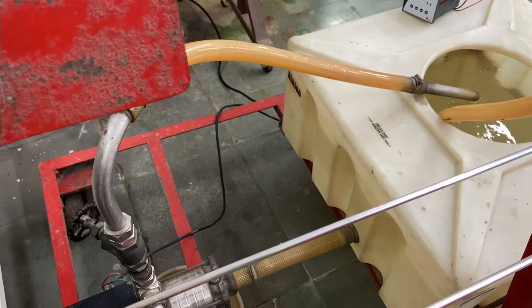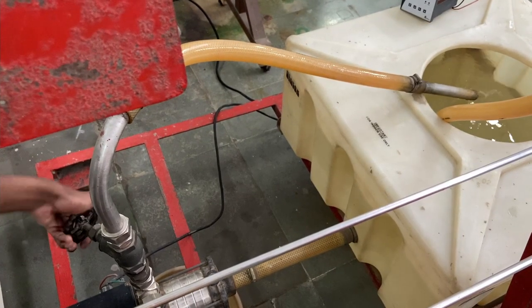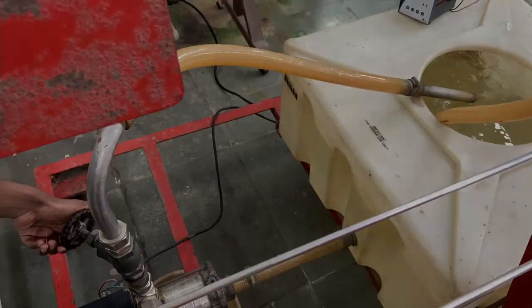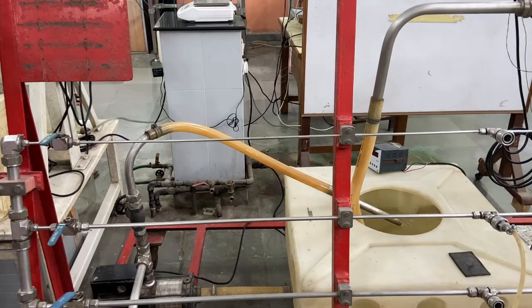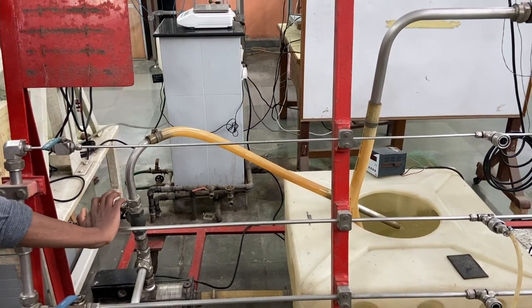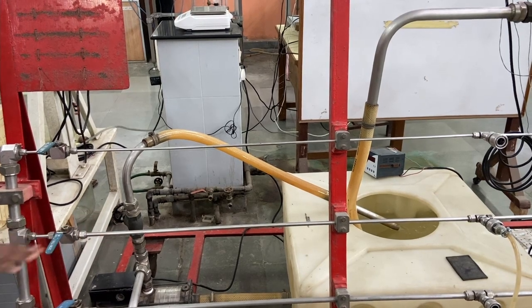The minimum flow rate is achieved by opening the bypass valve to the full extent. The ball valve at the inlet should not be used to control the flow rate. It is mainly used as an on-off valve.